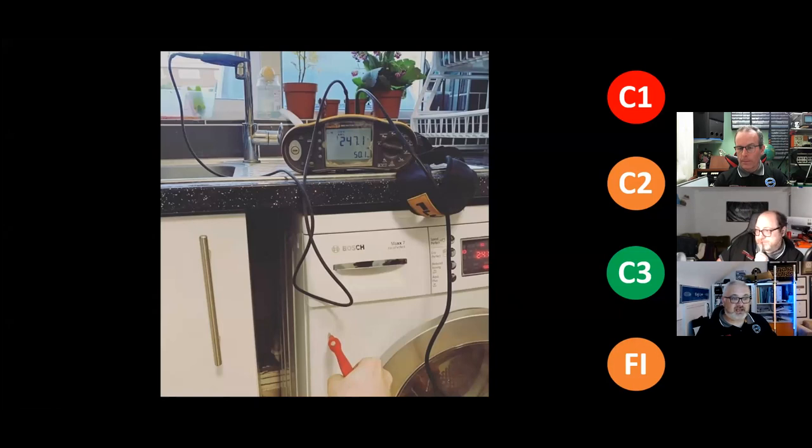Interestingly, again, another tease really, there is now more noise in the DNOs about using voltage contact testers on fixed equipment, even on DNO heads now because of tracking across the heads, but we'll cover that in another webinar. So just be mindful. It's literally a safety message. Be mindful, careful what you're touching, and listen to the user of the installation and the concerns that they have. It might even be worthwhile asking if you get any tingles off any equipment performing as it shouldn't. I do remember doing those checks. If someone says, I'm getting tingles, sometimes that's because they're not touching a very good 0 volt reference, but they're actually touching mains voltage.